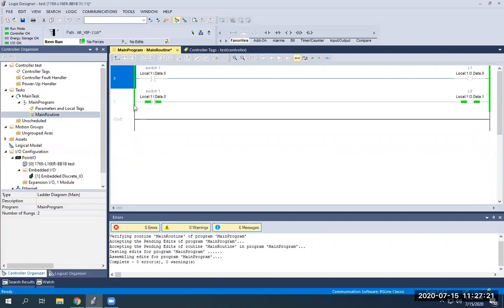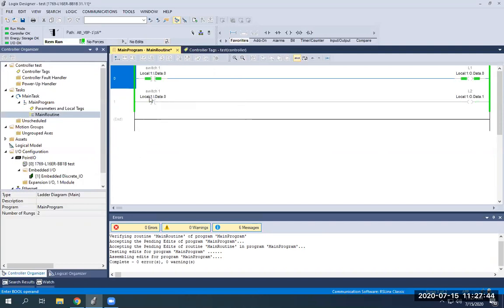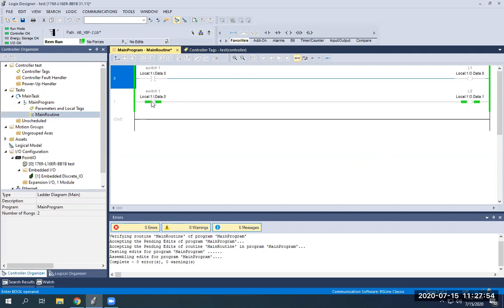So in a PLC, you can make switches do multiple things. Notice how light two is on. Switch one is de-energized up here, but it's energized down here. Like in electrical circuits or basic electricity, an XIC acts like a normally open switch, and an XIO acts like a normally closed. So if I turn on switch one, it de-energizes your XIO and energizes your XIC and turns on light one. And then if I turn it back off, it energizes your XIO down here and turns on light two. So switch one actually controls both lights. And if you can see the I/O interface that I'm flipping the switch on, you'd see the lights switching back and forth just like they are on the program. You can make several different things happen with only minimal amounts of inputs and outputs, but this is just one way to show you that switch one can be used for two different purposes to control two different outputs.